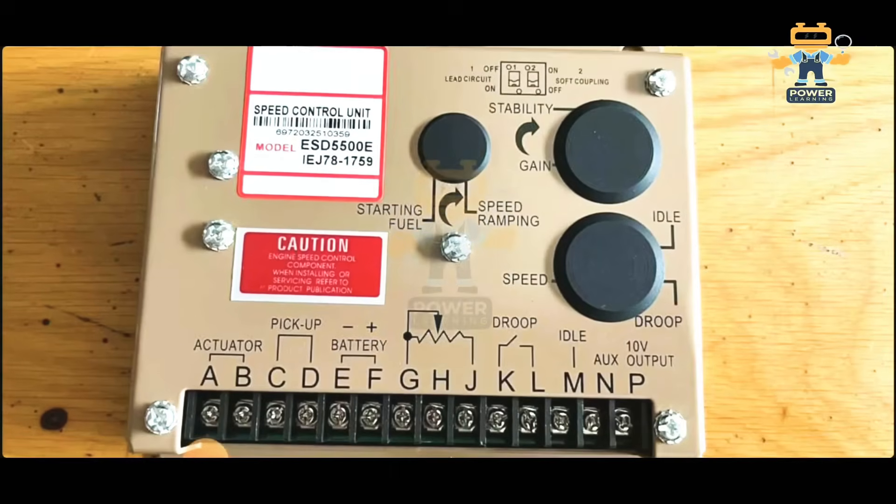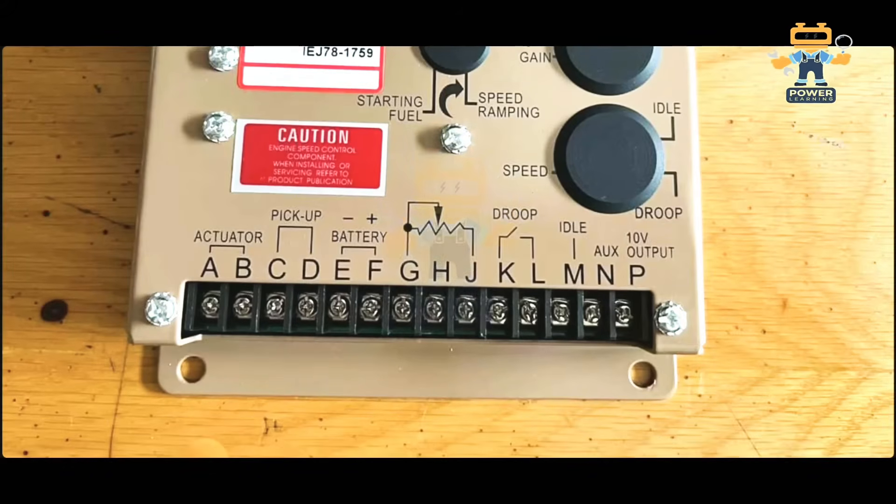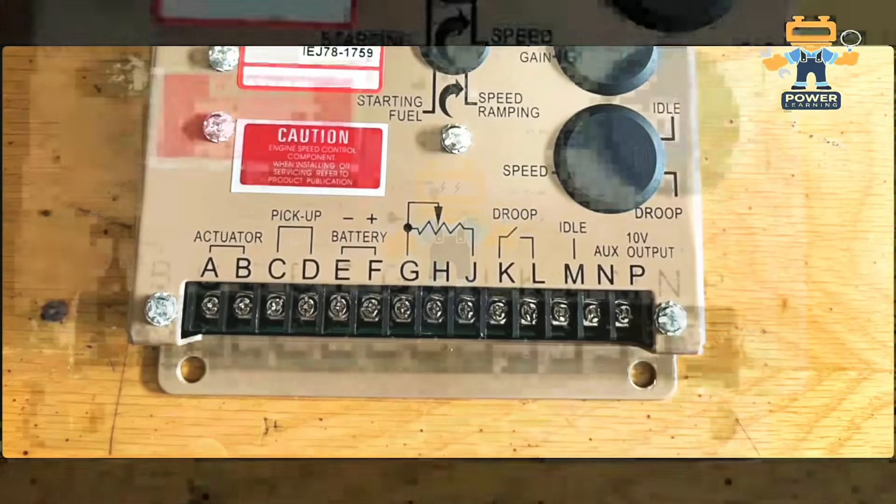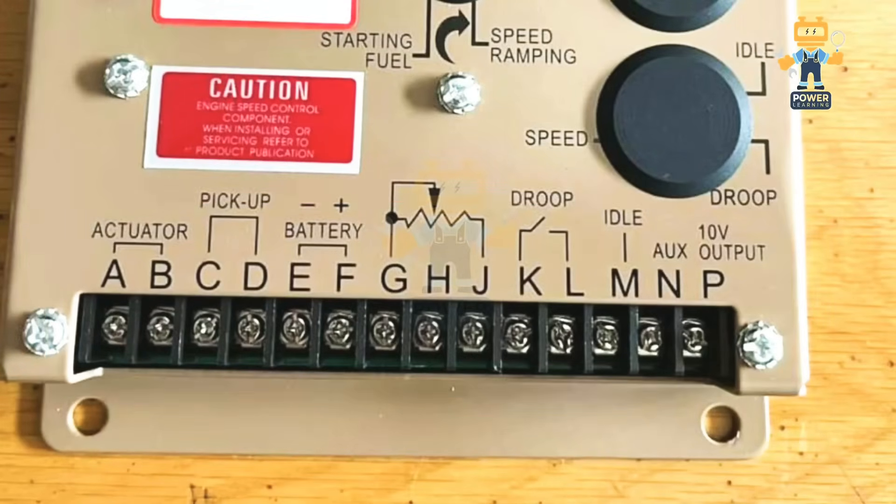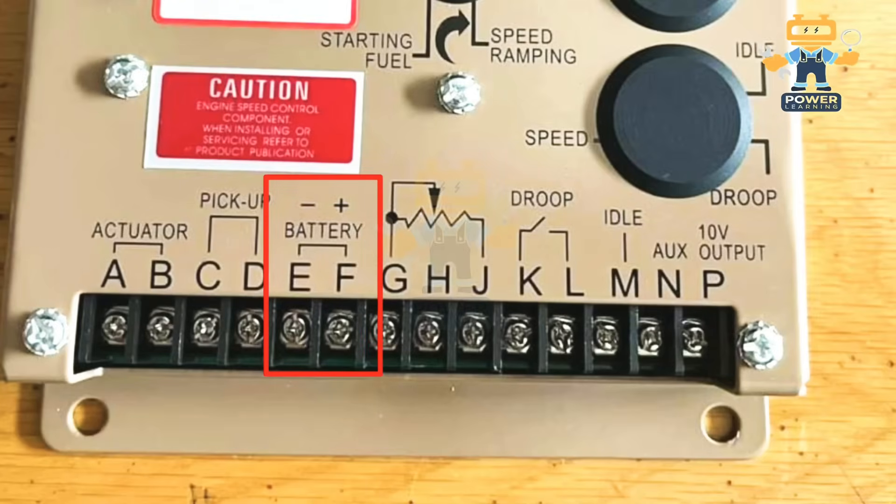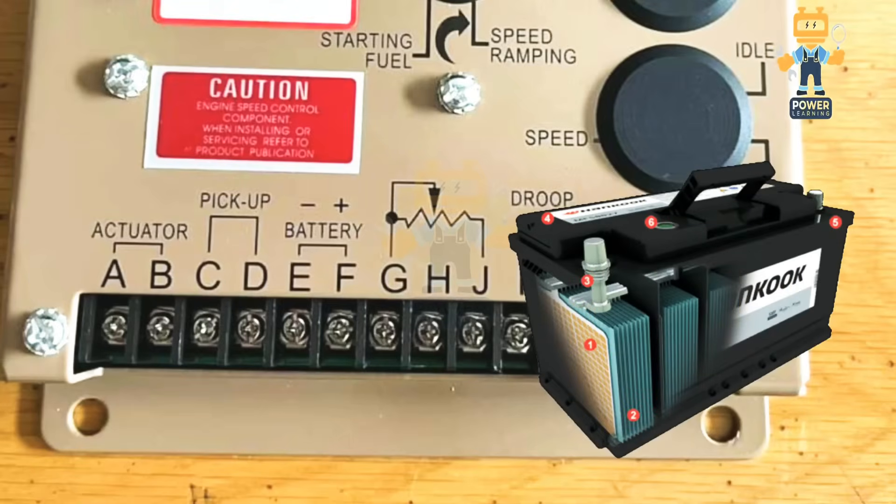First of all, it's written actuator - so actuator is terminal A and B. Pickup is terminal number C and D. Battery positive and negative is E and F. First, whenever we are connecting this controller, we have to give power supply to power it up. You will connect 12 volt or 24 volt to this controller on battery positive and battery negative terminals.